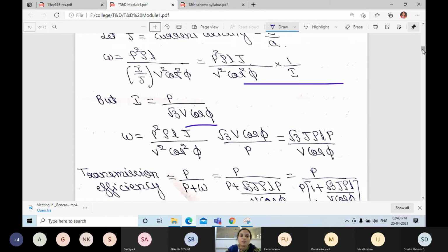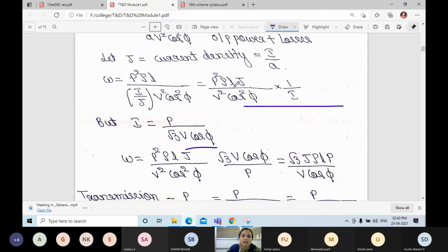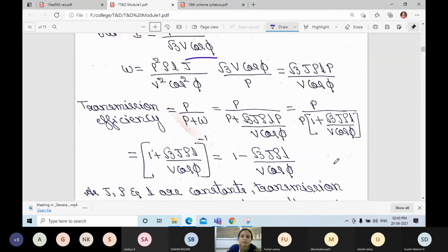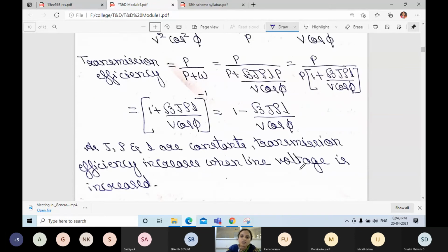W formula, we already know this formula. Just substitute I is equal to P divided by square root of 3 into V into cos phi, and you get the value of W. P divided by P plus W, substitute the value of W. From that equation we will get 1 minus square root of 3 J rho L divided by V cos phi. They have written it to the power of minus 1, which means 1 divided by 1 plus square root of 3 into J into rho L divided by V cos phi. They are saying that J, rho and L are constants.